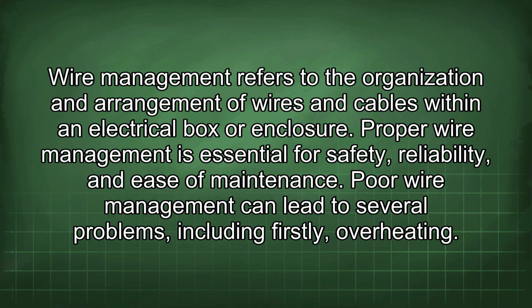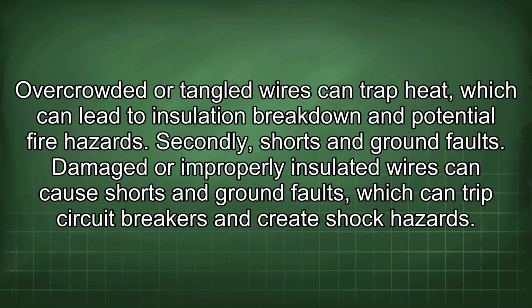Wire management refers to the organization and arrangement of wires and cables within an electrical box or enclosure. Proper wire management is essential for safety, reliability, and ease of maintenance. Poor wire management can lead to several problems, including firstly, overheating. Overcrowded or tangled wires can trap heat, which can lead to insulation breakdown and potential fire hazards. Secondly, shorts and ground faults. Damaged or improperly insulated wires can cause shorts and ground faults, which can trip circuit breakers and create shock hazards.